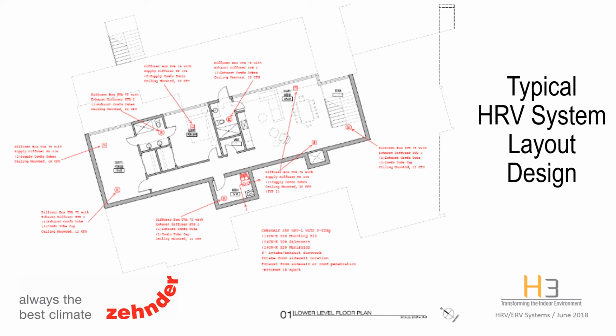Commissionings can also be requested via the portal, but please make sure systems are wired and connected prior to the agent being scheduled, as they are not contractors or installers. They are commissioning agents. They are there to program your controller, set up boost function, bypass settings, and balance flows pursuant to design requirements. A system must be properly installed to function pursuant to the design.